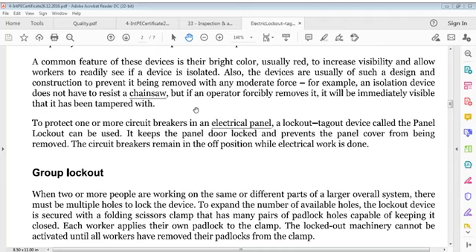Usually red, to increase visibility and allow workers to readily see if a device is isolated. Also, devices are usually of such a design and construction as to prevent removal with moderate force. For example, an isolation device does not have to resist a chainsaw, but if an operator forcibly removes it, it will be immediately visible that it has been tampered with.